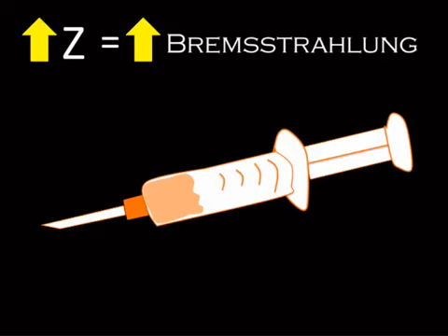Yttrium-90 would be a classic example, and because you can't just have the techs holding onto the syringe of this stuff with their hand, they put these shields on. You may say, well, I want the thickest shield possible. Well, I want a lead shield. Well, lead has a very high Z, and that's going to generate a bunch of this braking type of radiation. That's actually going to make things worse, because it's going to actually become an X-ray generator, essentially.